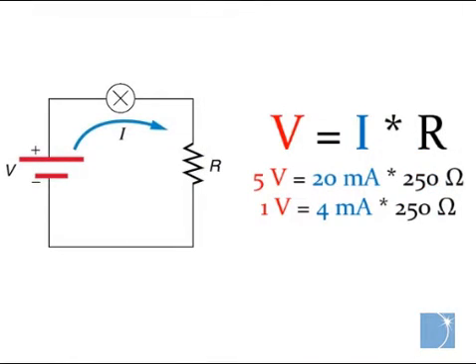Using Ohm's law, the 4 to 20 milliamps flowing through the 250 ohm shunt resistor will yield 1 to 5 volts full scale.